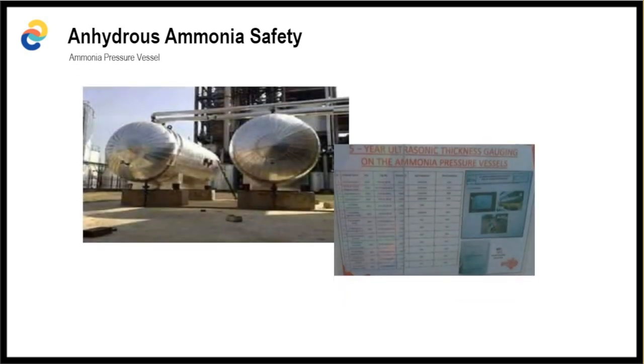Okay, ammonia pressure vessel. Ammonia pressure vessels should comply with the ASME Boiler and Pressure Vessel Code, Section 8, Division 1. This covers the design, fabrication, inspection, and testing during construction of the pressure vessel. Manufacturers producing pressure vessels shall provide data affixed on the nameplate. Also, pressure vessels should have safety features such as a relief valve installed. It should be sealed and set by the manufacturer, and also of the approved type and capacities, whether it's for the low pressure side or the high pressure side.